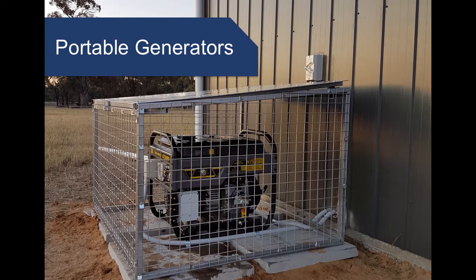On some off-grid systems, we put in portable generators. This is an example of a portable generator. Most of the time, we're recommending for off-grid customers to get a good quality diesel unit from a brand name supplier. Most of them, we're recommending get a sound attenuated weatherproof canopy. But something like that, quite often you're looking at $10,000 for a good diesel generator. Something like this, I think, was more like $6,000 or $5,000.